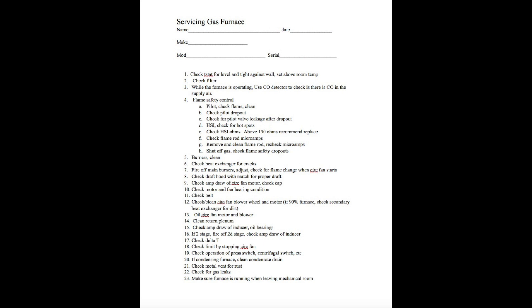If it's a two-stage furnace, you want to fire off both stages. You want to run it in low stage and high stage to be sure all things work as they should when it goes to that second stage. While the furnace is running, you're also going to check delta T. Delta T is the temperature difference between the return air and the supply air. It should be below the model plate rating specs, well below them actually. The amount of temperature difference across the coil or delta T depends on the furnace and the blower speed setting, but it should be below the ratings that are on the plate.